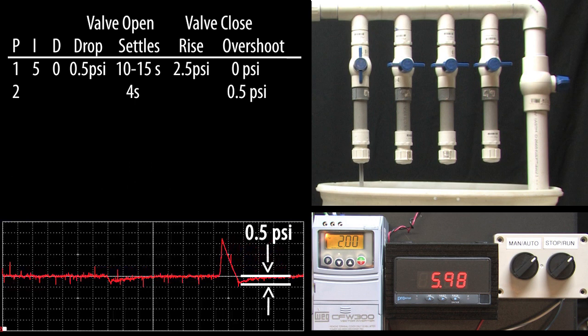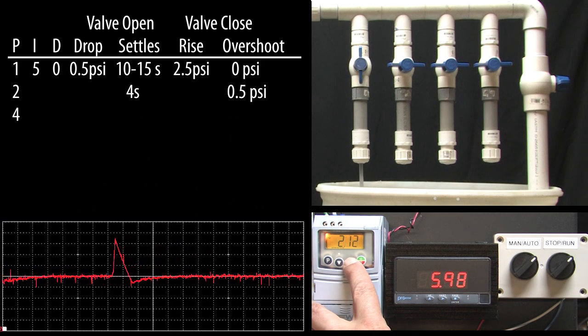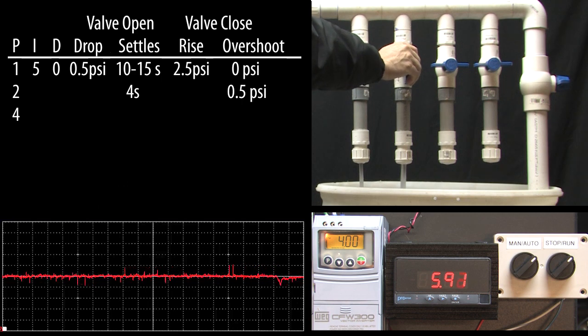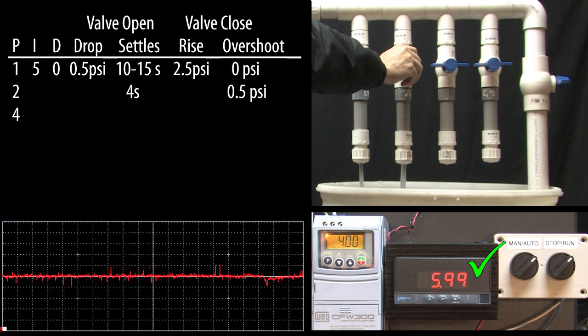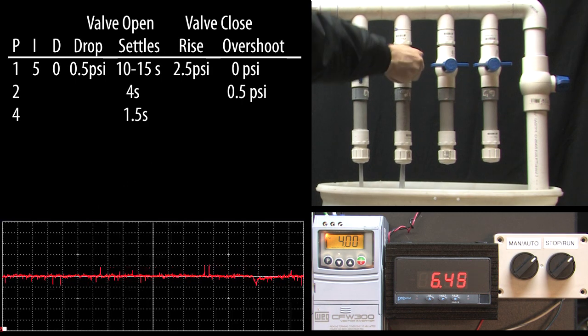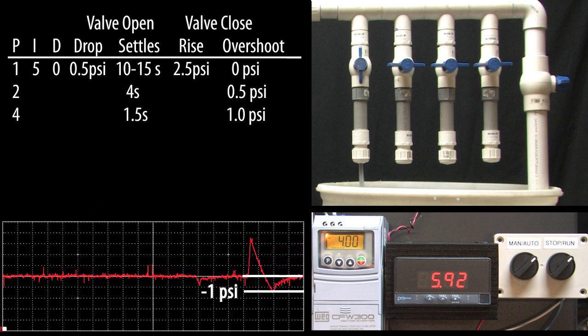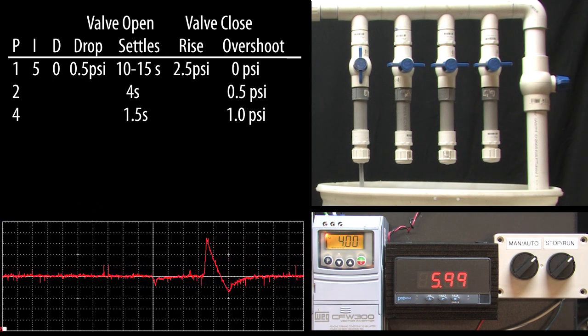Interesting. Let's double P again to 4 and open a valve. Wow! The valve opening recovers in only one and a half seconds. But the valve closing is now overshooting the 6 psi goal by over 1 psi so it's taking even longer to recover. If you don't have abrupt valve closings then this won't be an issue and a P of 4 might work great for you.